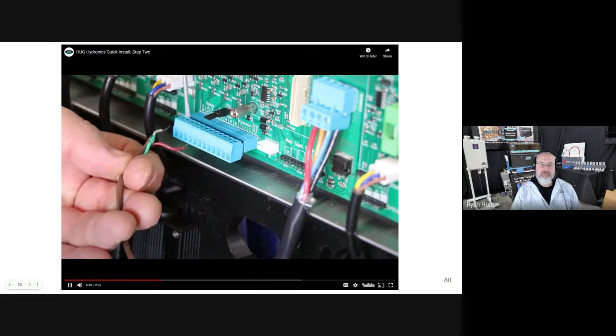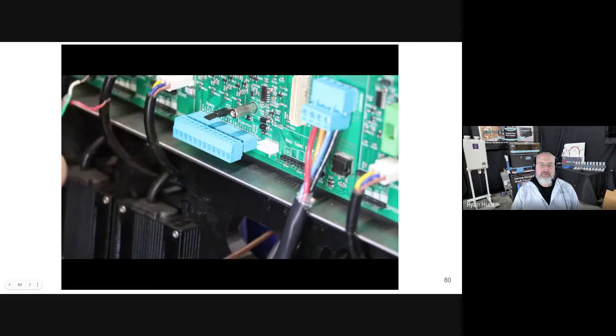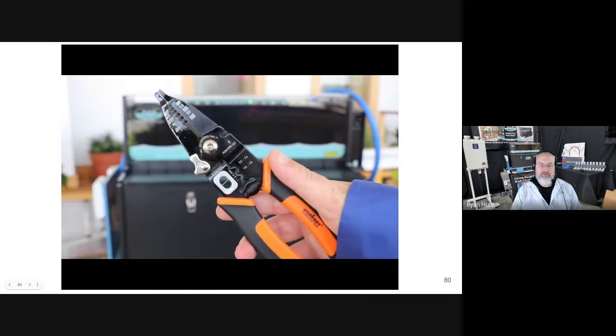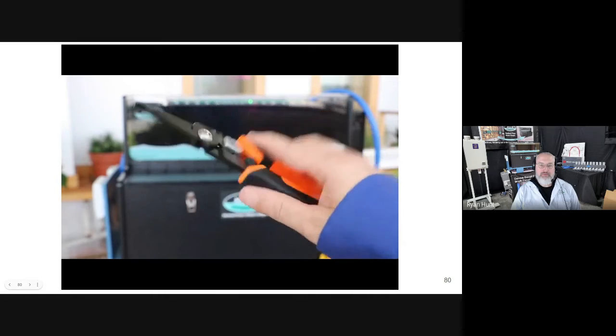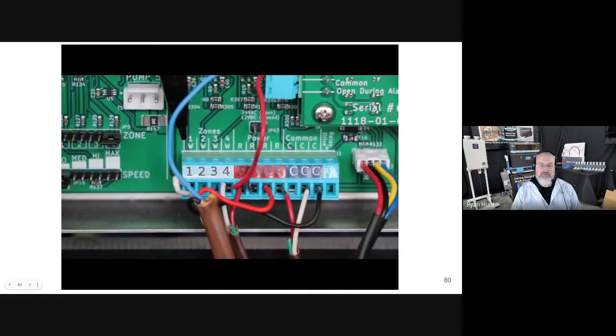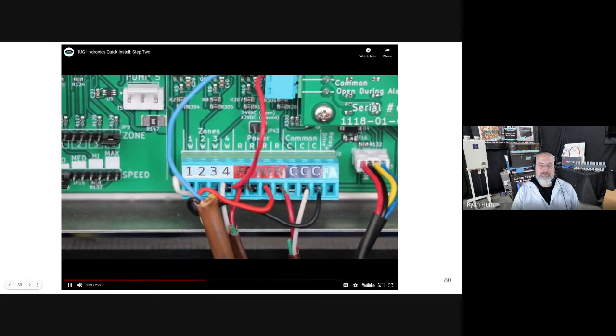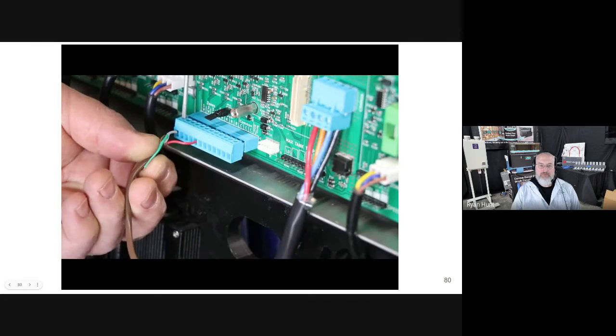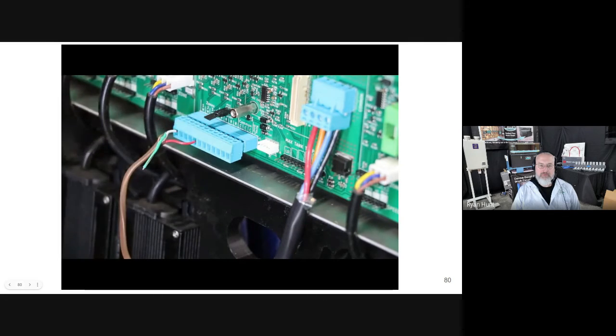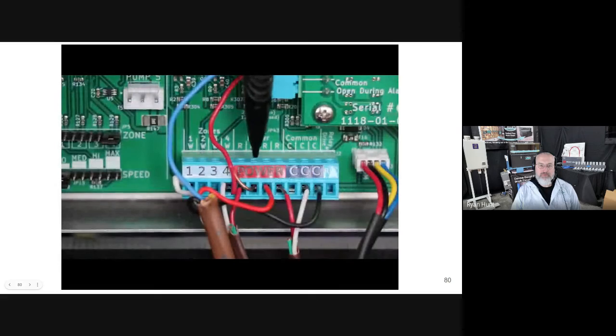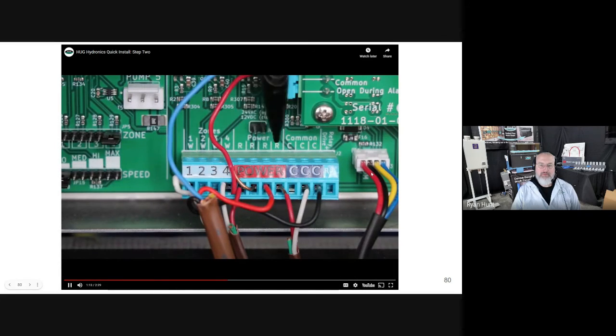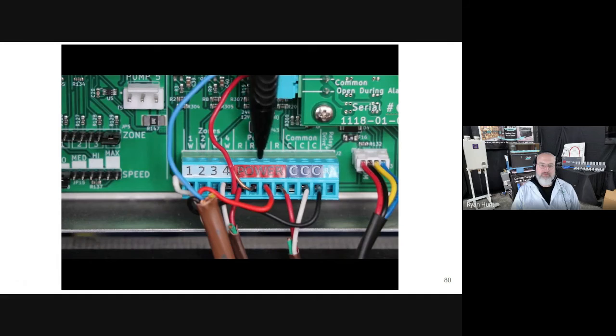Now, for each thermostat, we're going to connect the wires. Strip the end of the thermostat wires. If you have one, stick the white wire in the connector for the appropriate thermostat zone number. Then, tighten the little screw and turn to the right, as tight as it will easily go. This should hold the wire securely and make the electrical connection possible. The red wire will go in one of the power terminals. Tighten as with the white wire. Do not plug the connector back into the control board yet.